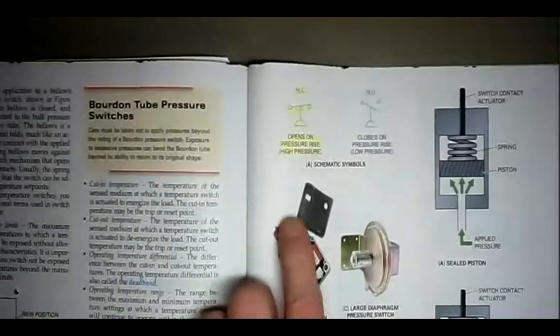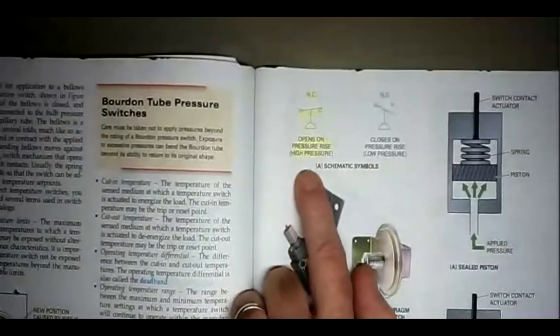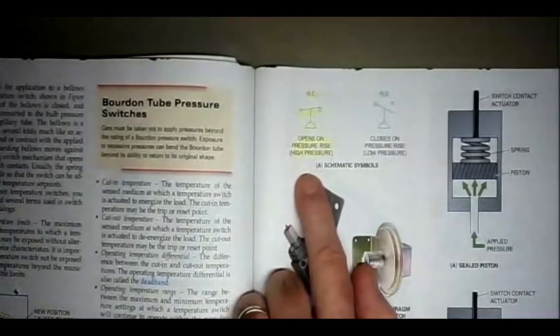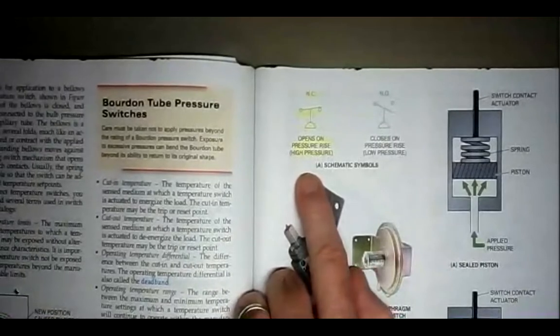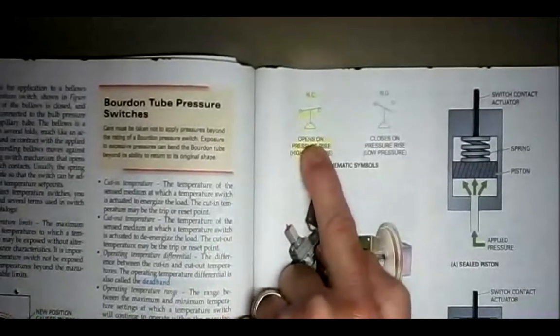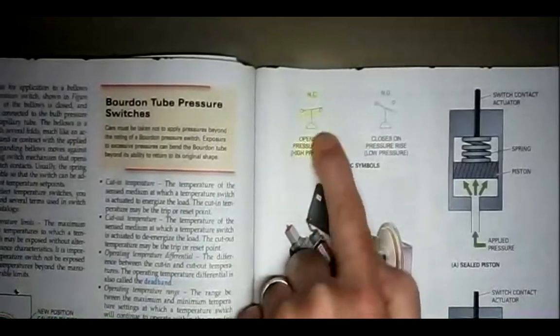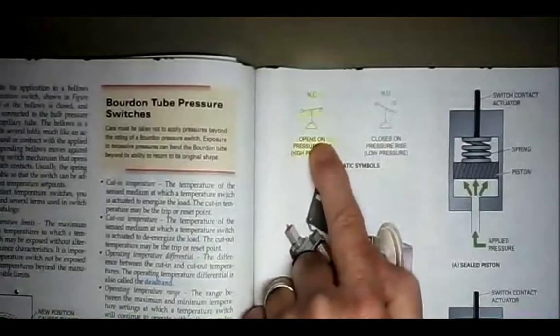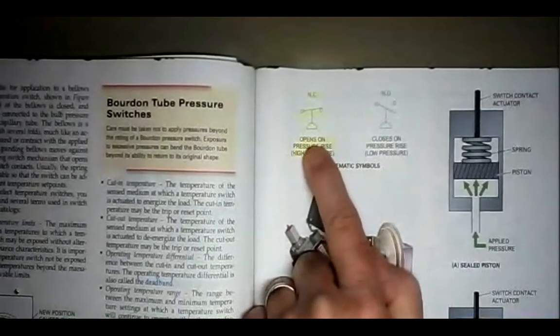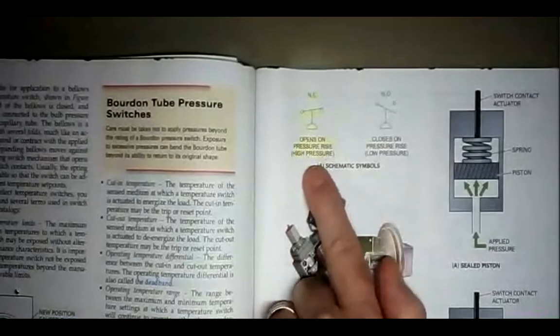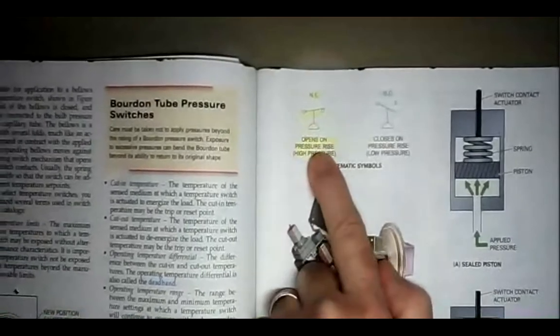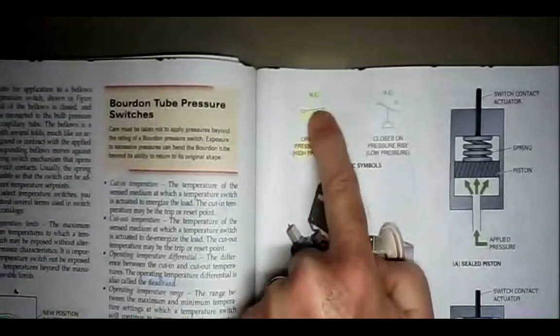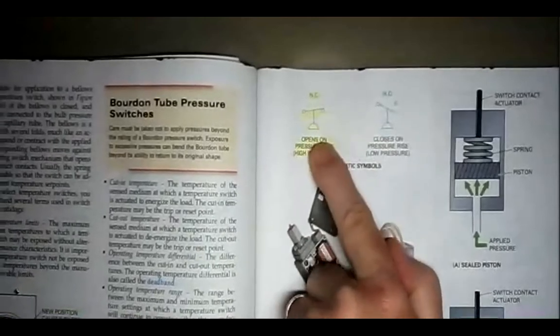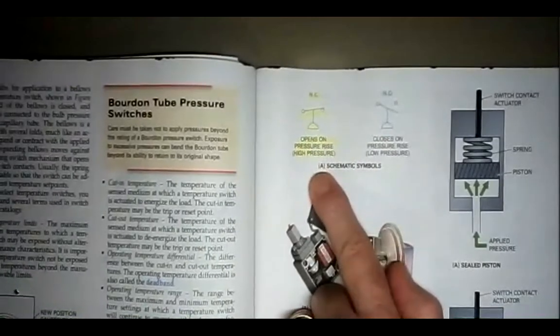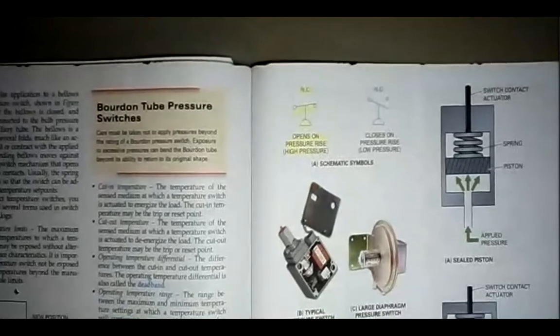On page 43, here's an example of a pressure switch. And the way I was taught is that you imagine one of those old-fashioned oil cans that are curved on the top and flat on the bottom, and you push on them and you get oil out. You have to put pressure on the bottom. So that's a pressure switch. This is a normally closed pressure switch. Again, the contact bar is on top of the node. That's normally closed. It opens on pressure rise.